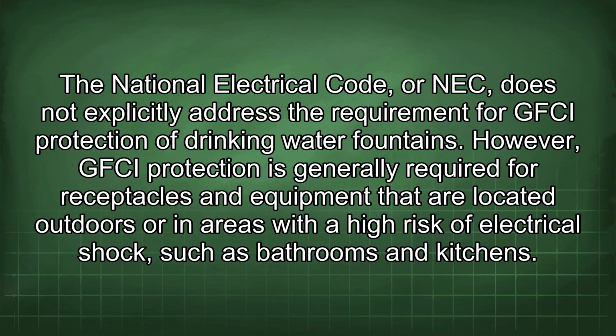The National Electrical Code, or NEC, does not explicitly address the requirement for GFCI protection of drinking water fountains. However, GFCI protection is generally required for receptacles and equipment that are located outdoors or in areas with a high risk of electrical shock, such as bathrooms and kitchens.